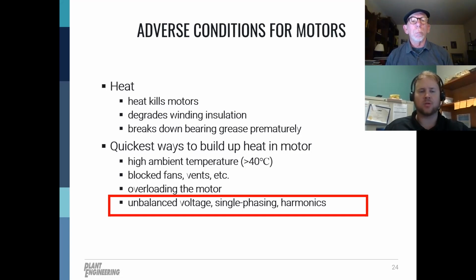High ambient temperature, blocked fan, or if the motor has cooling vents, blocked cooling vents. Overload on the motor, above rated load. Improperly sized for an application. And then, of course, power quality issues. Typical power quality issues include voltage unbalance, so unbalanced voltage right at the motor terminals, single phasing, or if you have relatively close in proximity nonlinear loads that may lead to voltage and current distortion, harmonics. We're going to talk about that in the power quality section a little more.